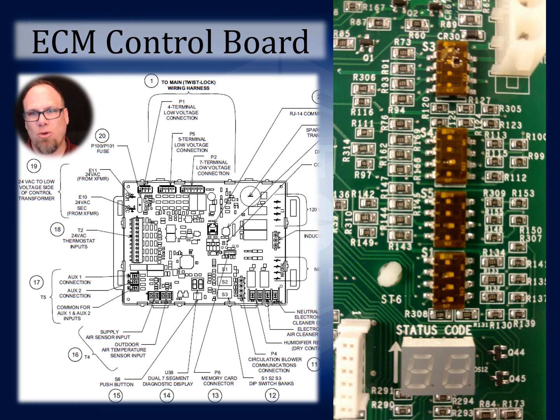As you look at the actual control board that I took a picture of here on the right-hand side, if you look close, in the upper left-hand corner of each of those switch banks, they're not in order. The one at the very top, spaced away from the other three, is S3, so switch bank 3. Then after that comes switch bank 4, and then 5, and the one very lowest on that totem pole is switch bank 1. Now you can see that those switches on those switch banks, they go in one position to the other position. One side's on, one side's off, and different configurations of on and off give you different values in programming for how the controls in the rest of that furnace operate, particularly in this case for our variable speed motor.